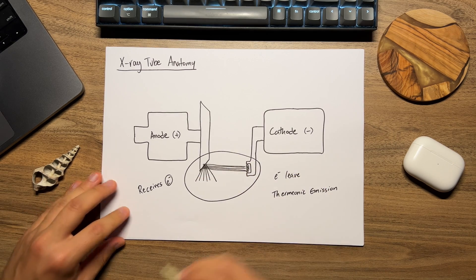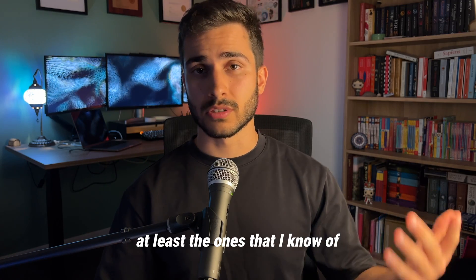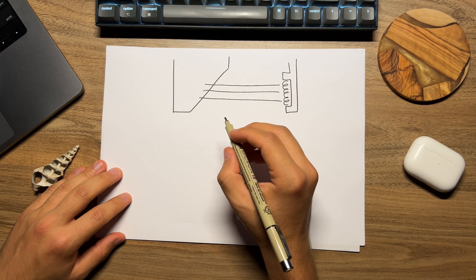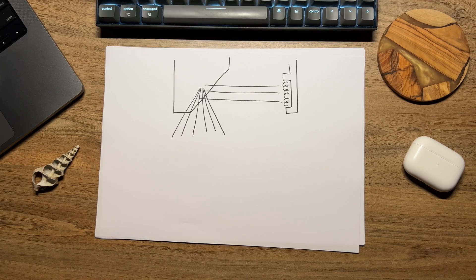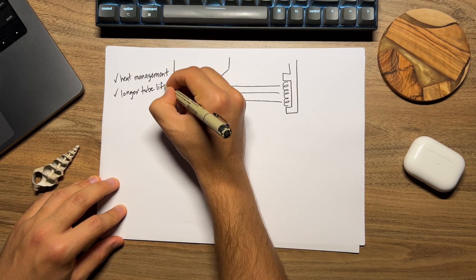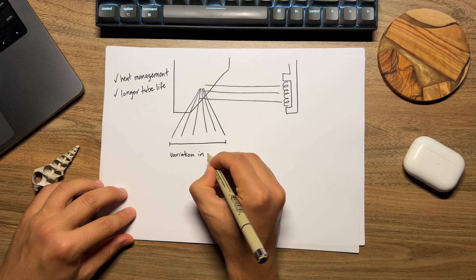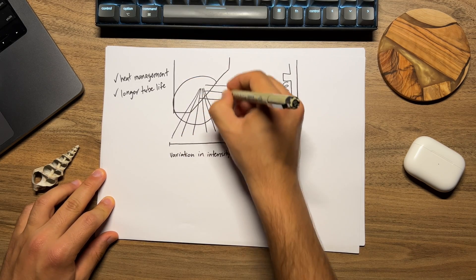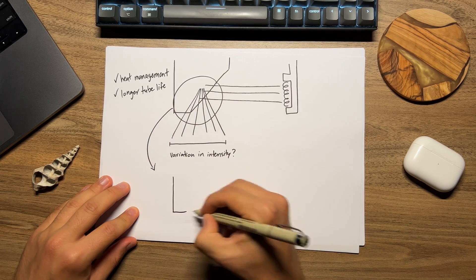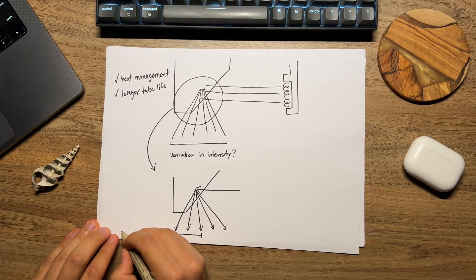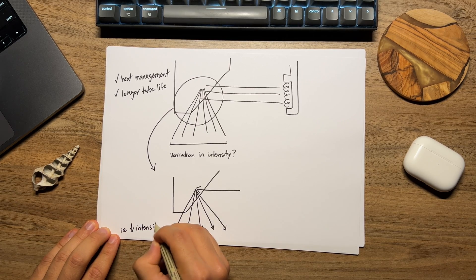The anode heel effect is a consequence of the geometry of the anode. In most x-ray tubes, the anode is angled relative to the beam's path, so it doesn't just bounce back. This angulation is required to allow for better and more efficient heat management, which prolongs the tube's life. However, because of the geometry of the beam as it hits the anode, there's a variation in x-ray intensity across the beam — with lower intensity on the anode side, the heel, and higher intensity on the cathode side. This intensity variation is due to the absorption and attenuation of x-rays in the thicker part of the anode material, so more of those electrons are absorbed on the anode side than on the cathode side.